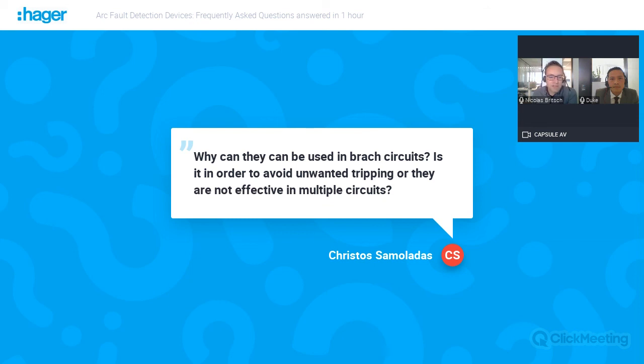Okay, so this question: why can they be used in one circuit? Is it in order to avoid unwanted tripping, or are they not effective in multiple circuits? I think we have answered this during the session. The question relates to the protection of multiple circuits. As we have said before, it is first written in the standard, but the reason is that it ensures a good level of protection as well as limiting the exposure to disturbances.